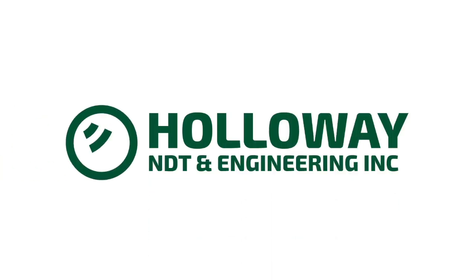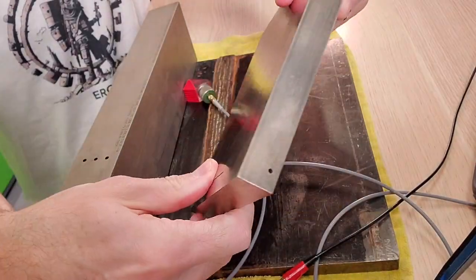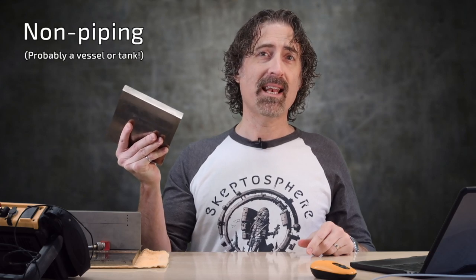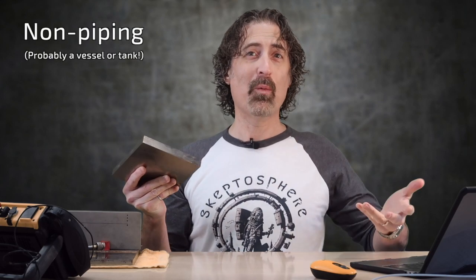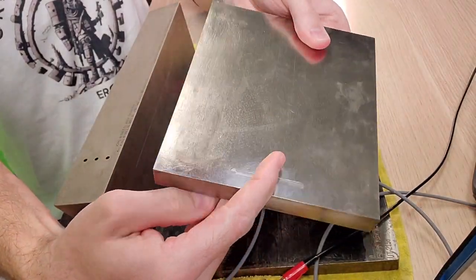Today, I'm going to take a look at the sensitivity effects of surface condition on calibration blocks. You've probably got one of these. This is a 3/4 inch ASME basic calibration block. These are used for non-piping applications in ASME, which is a roundabout way of saying mostly vessel stuff. A lot of these look just like mine. There is a shiny nickel plating on it to prevent corrosion.